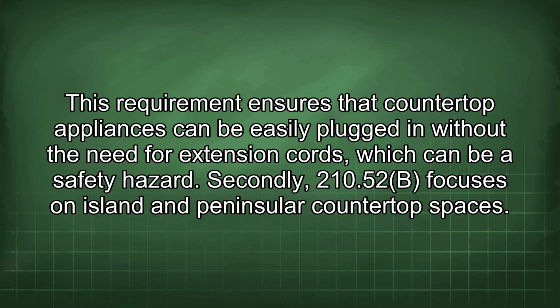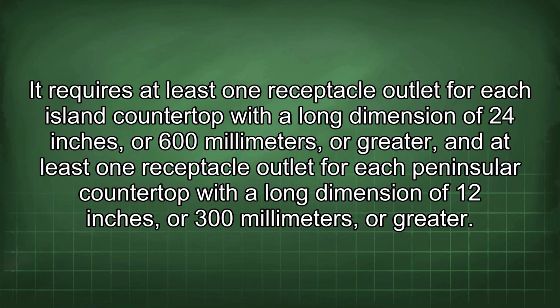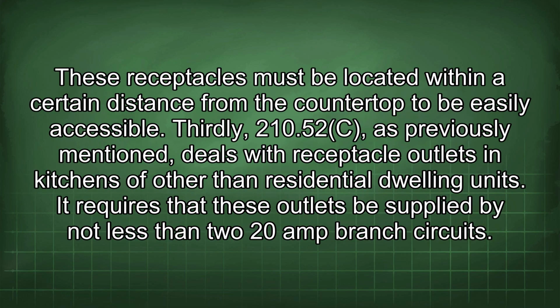210.52b focuses on island and peninsula countertop spaces. It requires at least one receptacle outlet for each island countertop with a long dimension of 24 inches, or 600 millimeters, or greater, and at least one receptacle outlet for each peninsula countertop with a long dimension of 12 inches, or 300 millimeters, or greater. These receptacles must be located within a certain distance from the countertop to be easily accessible.